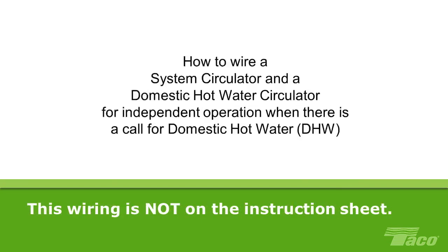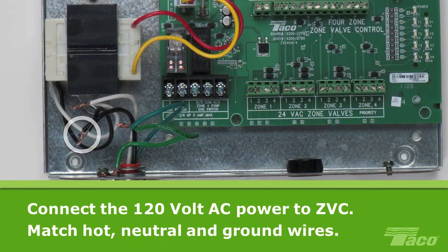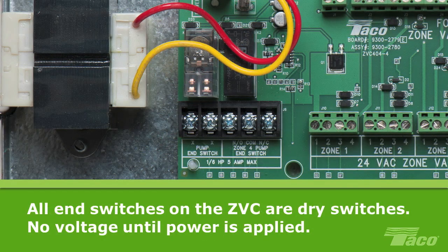How to wire a system circulator and a domestic hot water circulator for independent operation when there is a call for domestic hot water. This wiring scheme is not on the instruction sheet. First, connect the 120V AC power to the zone valve control, ZVC, matching the hot wires, the neutral wires and the ground wires. Before continuing, remember that the end switches on the Taco zone valve control are all dry switches. This means there is no voltage at the switch until power is applied.